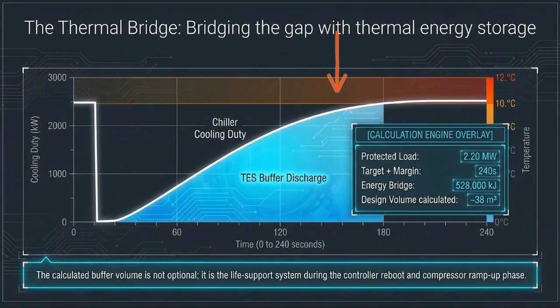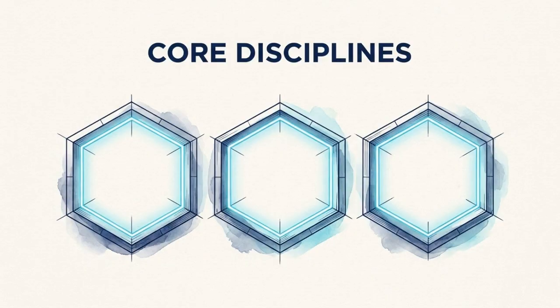Above, the flat orange line, the IT load, never drops. Servers keep pumping heat. The empty void between them is a 3-minute transient window where the plant absorbs no heat, risking rapid thermal runaway. Surviving this exact transient window requires strict engineering across 3 disciplines.